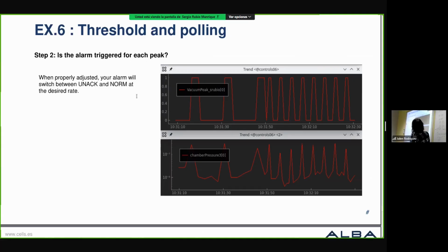This is an extreme situation because we do not have peaks every second or every 10 seconds. But for example, we can have in an RF chamber problem with an arc that happens sometimes, and it's a very brief peak. And we just want, even if the RF chamber continues working okay after that, to receive an alarm for each arc because we want to count how many times it happened during the week to evaluate the product. So this is a way in which you can do it.